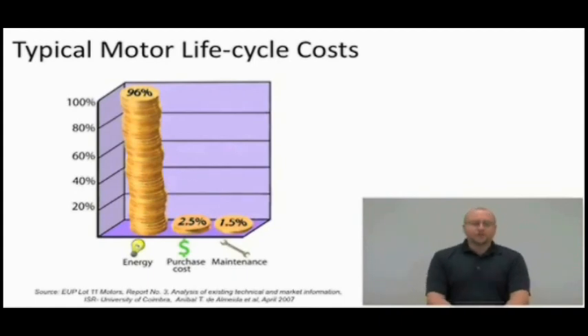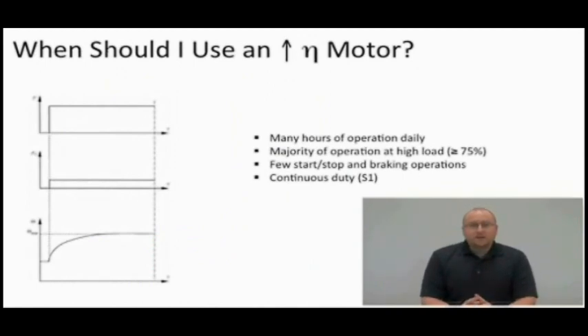So when should you use an energy efficient motor? Well, you're only going to be able to save energy if you're running. So it's going to be a motor that you turn on and it's running all day or runs for a long period of time. It's going to be a motor that doesn't cycle. You turn it on and let it run. S1 duty, continuous duty. You want it to be loaded properly. Remember, we were looking at that efficiency versus loading curve. If it's really underloaded, my efficiency goes down. I don't want that. So you want your proper loading conditions. You don't want to be cycling your load back and forth all the time, and you want an application where you turn the motor on and you let it run.